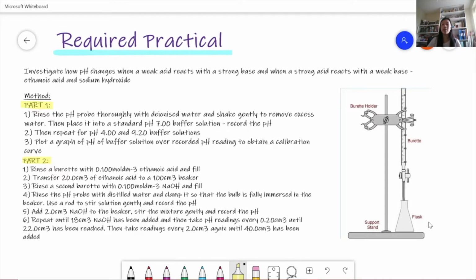So for part one, the first thing you do is rinse the pH probe thoroughly with deionized water and shake gently to remove the excess water. And we then place it into a standard pH 7 buffer solution. And then we record the pH, because the pH meter will be close to 7, but it might be slightly off. So we need to record that pH that it's measured. And then we repeat for pH 4 and 9.20 buffer solutions.